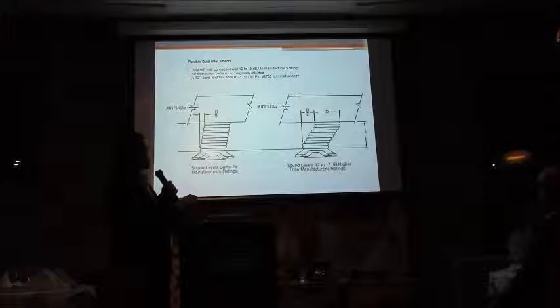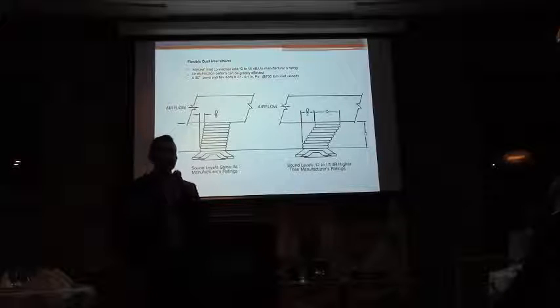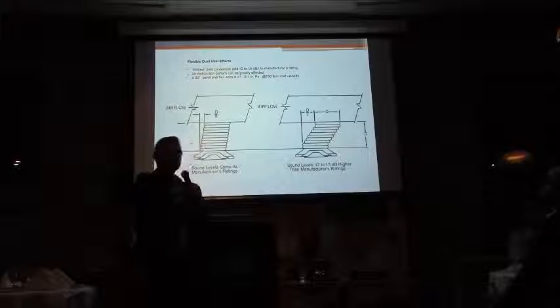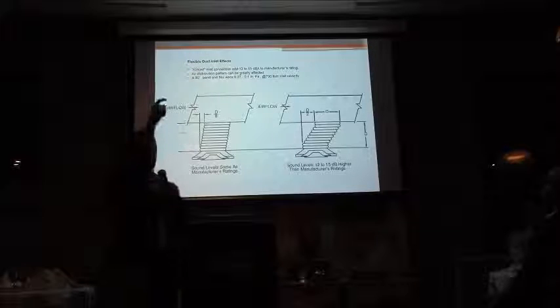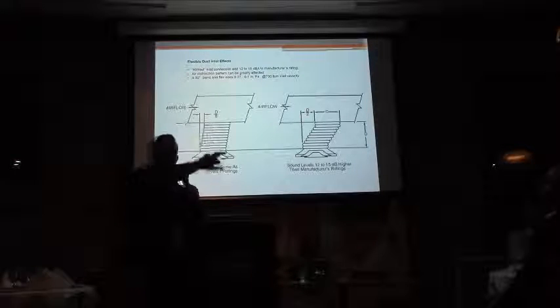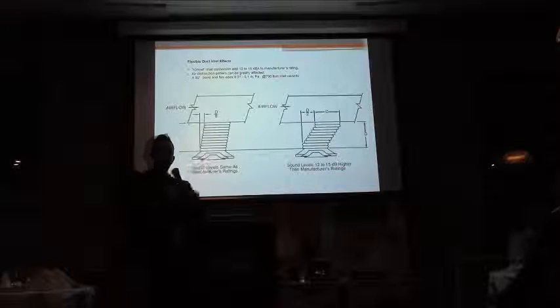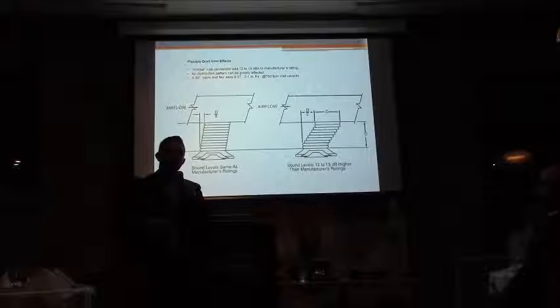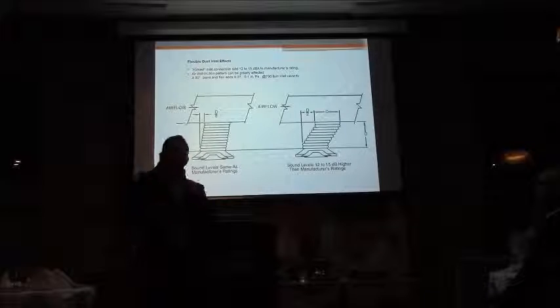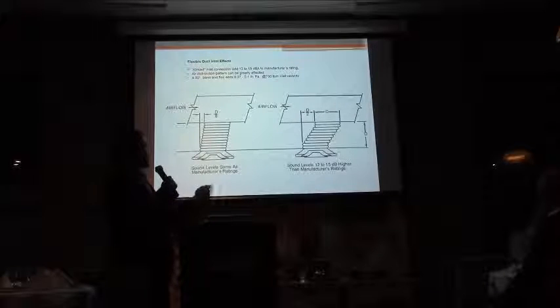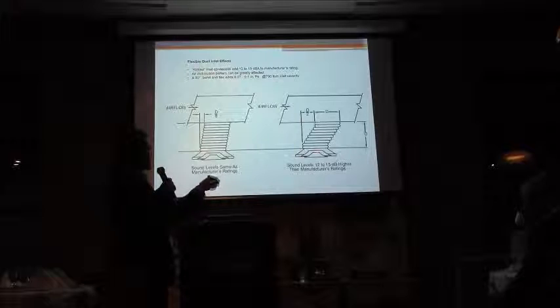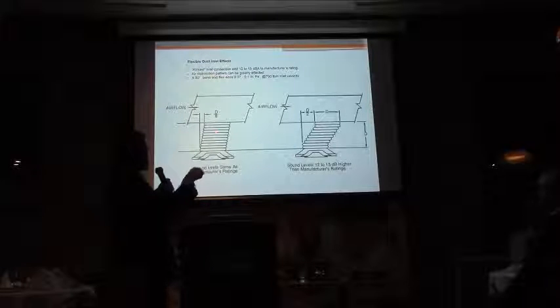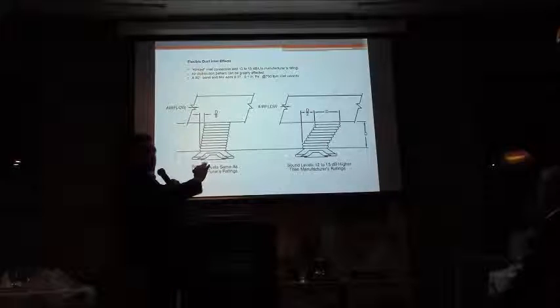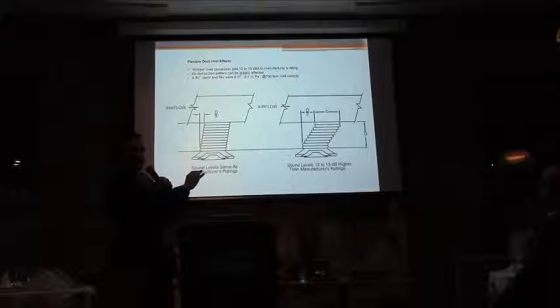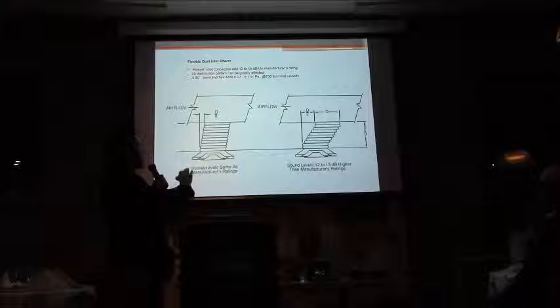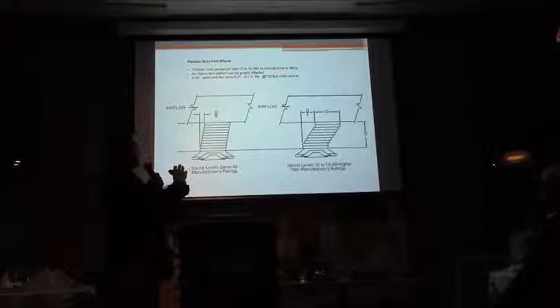So if you don't have a plenum, you're going to use a flexible connection and connect it straight to the inlet of your diffuser. So instead of being vertical, you're going to come in horizontally, probably, depending on the contractor, swirl around the diffuser a little bit because he doesn't want to cut the flexible duct, and then connect into the neck of your diffuser. So what that does is that you have a kinked inlet connection, somewhere similar to that here. It's not going to be straight, it's going to be more kinked. And all of that is coming from the engineering guides of any North American manufacturer. I'm not inventing this, I didn't even draw this, I took it straight from one catalog.